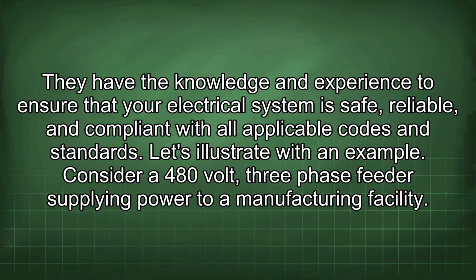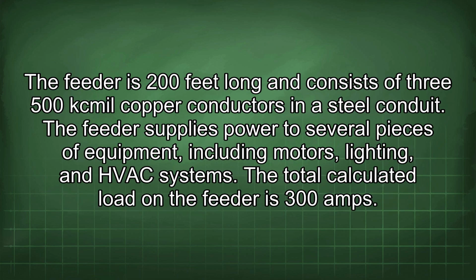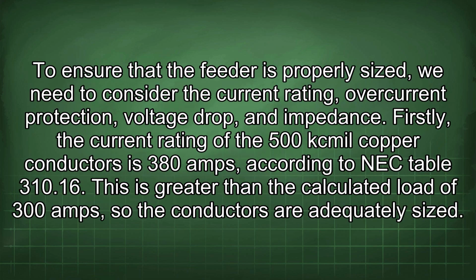Consider a 480-volt, three-phase feeder supplying power to a manufacturing facility. The feeder is 200 feet long and consists of three 500 kcmil copper conductors in a steel conduit. The feeder supplies power to several pieces of equipment, including motors, lighting, and HVAC systems. The total calculated load on the feeder is 300 amps.